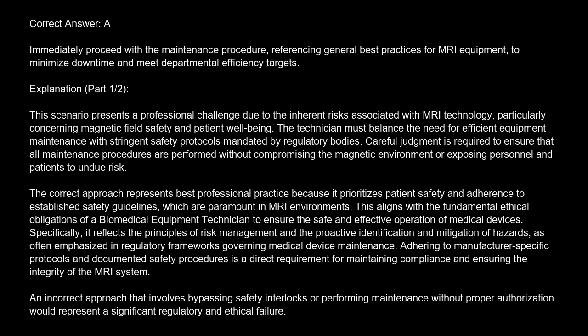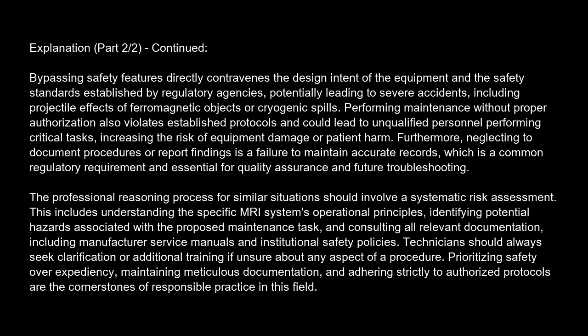An incorrect approach that involves bypassing safety interlocks or performing maintenance without proper authorization would represent a significant regulatory and ethical failure. Bypassing safety features directly contravenes the design intent of the equipment and the safety standards established by regulatory agencies, potentially leading to severe accidents, including projectile effects of ferromagnetic objects or cryogenic spills. Performing maintenance without proper authorization also violates established protocols and could lead to unqualified personnel performing critical tasks, increasing the risk of equipment damage or patient harm. Furthermore, neglecting to document procedures or report findings is a failure to maintain accurate records, which is a common regulatory requirement and essential for quality assurance and future troubleshooting.